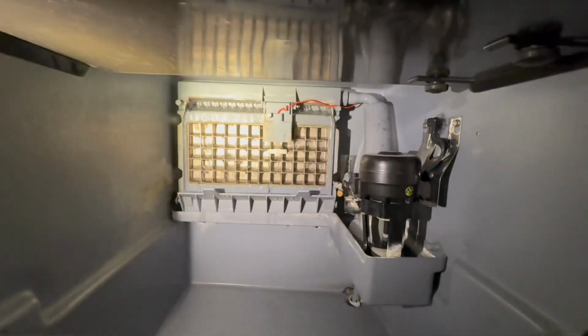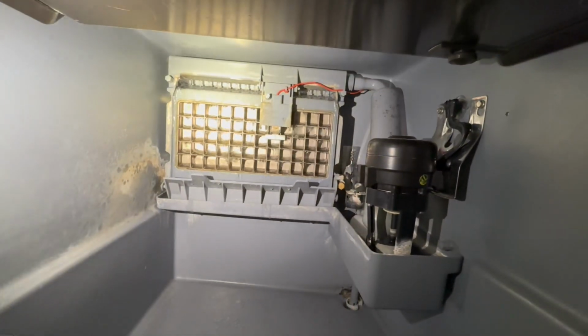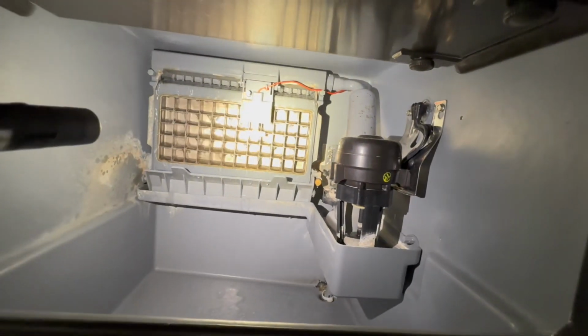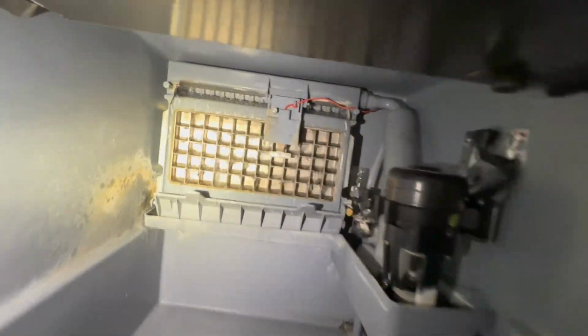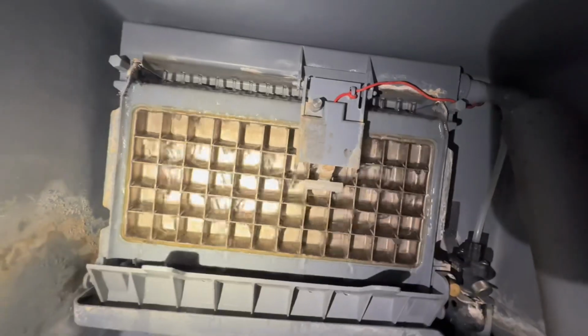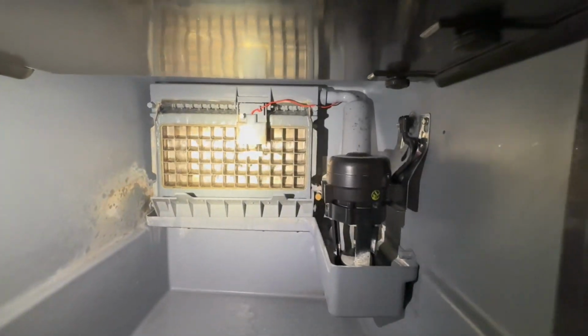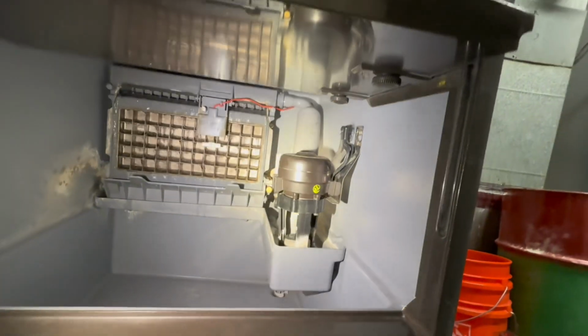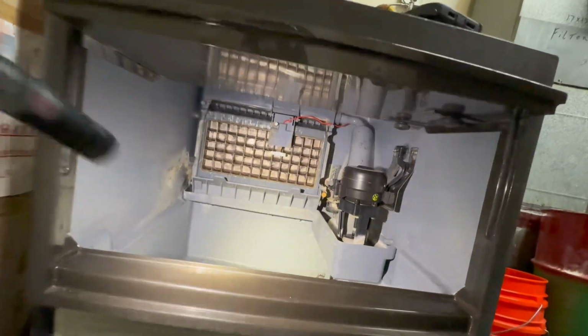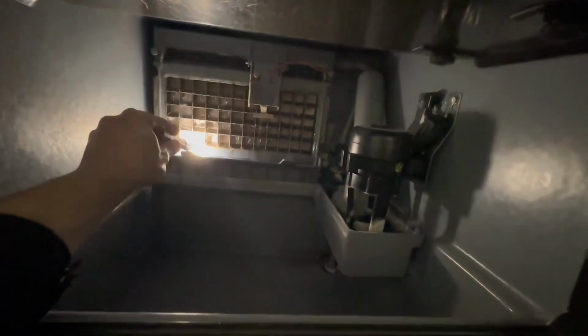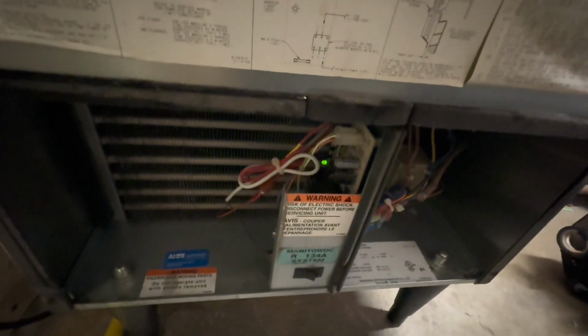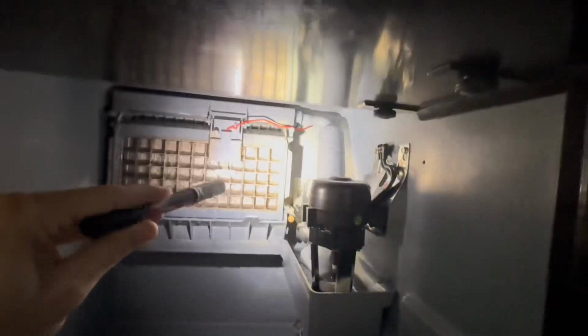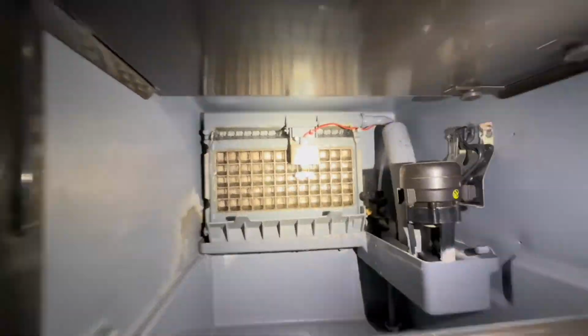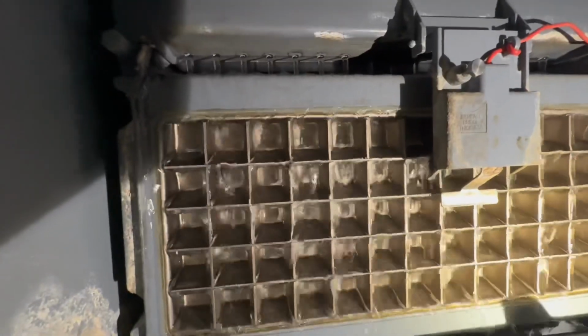It is kind of dirty up in there, but not anything too concerning, like not anything that's going to keep the machine from working. Ice thickness probe has a little bit of scale buildup on it. As you can see, the evaporator looks to be in good condition. It's not separating. One thing that I can check is the curtain switch. If I move this flapper up and down, does it trigger the light on my control board? Yes, it does. 12 minutes into freeze, we have a decent amount of ice forming on the evaporator.